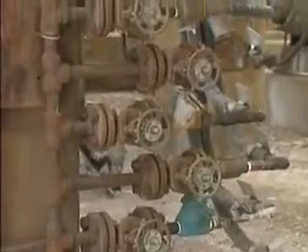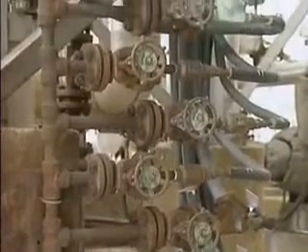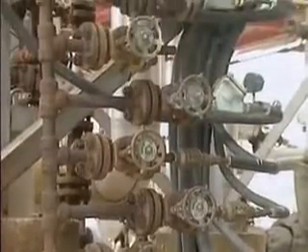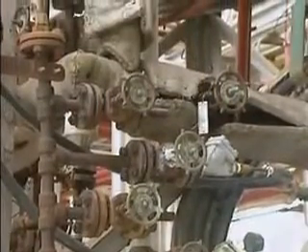or it may clear up questions about how the trap station has performed under certain operating conditions. After a steam trap station has been surveyed or inspected, the next step is to survey the individual traps in the station. Trap problems aren't always easy to detect, so a combination of different inspection methods may be used. Typically, a thorough trap survey combines information obtained by performing 3 types of inspections: temperature, sound, and visual.